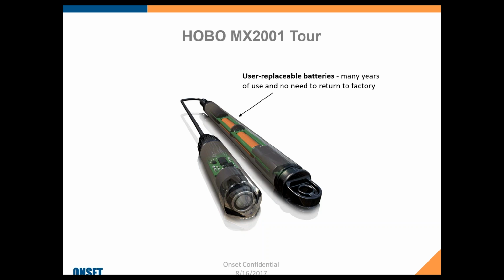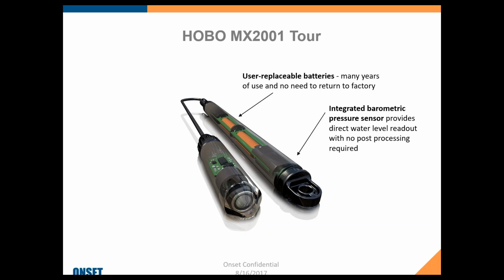No factory battery replacement required. The integrated barometric pressure sensor is now included in this logger, so you don't need that external source of barometric pressure data to get the barometric pressure compensation. The Bluetooth chip is also in the logger portion, which is mounted above ground.